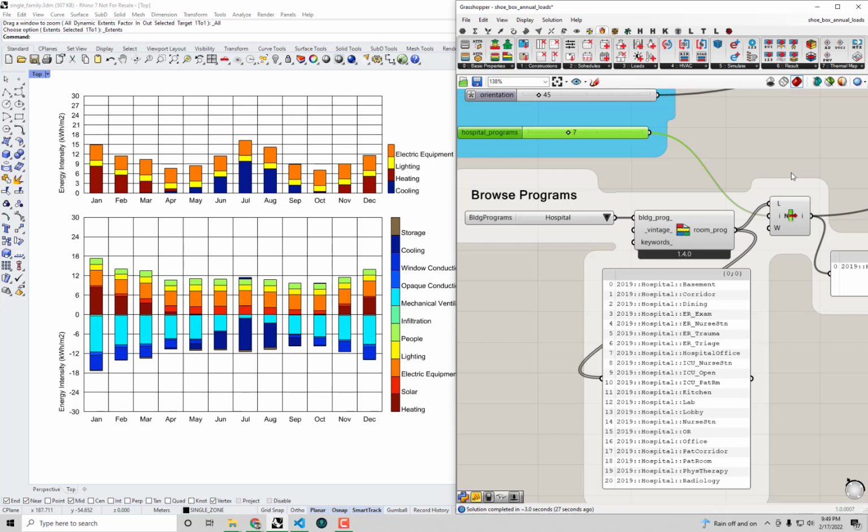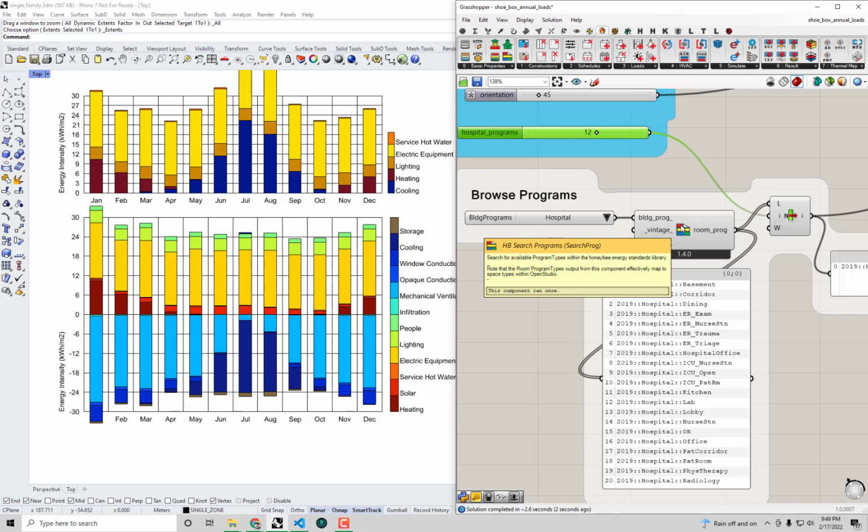You had something as intensive as a laboratory with a passive house wall, for example. And as you guys can see, if I were to take the lab in a hospital, which is number 12, and put on a passive house wall, maybe that would have been really nice if you did it for a residence, but that is an incredibly tiny drop in the bucket, barely doing anything compared to, let's say, trying to invest in heat recovery for the large amount of ventilation that you typically have in labs. So, all right, hopefully this puts everything in perspective.